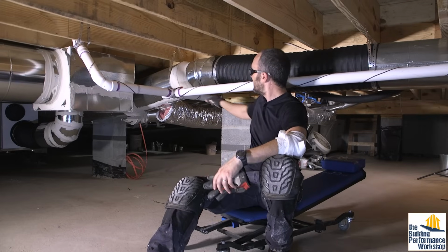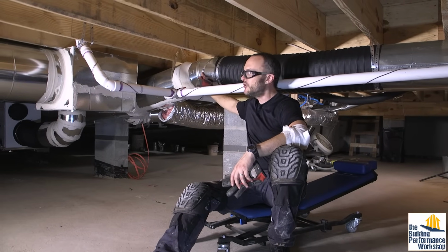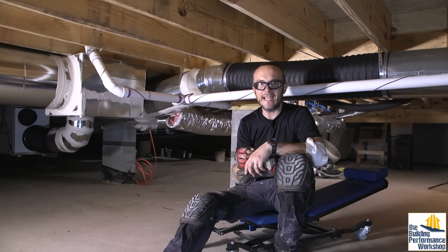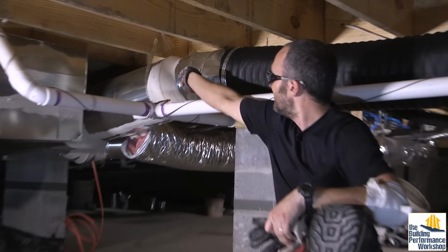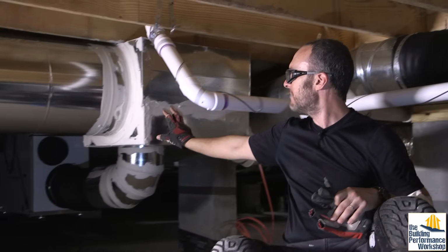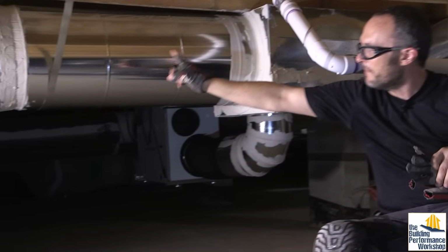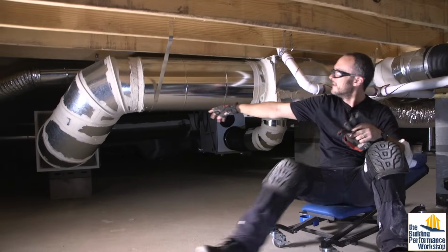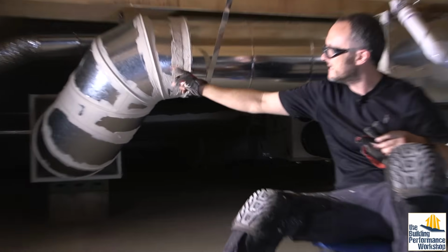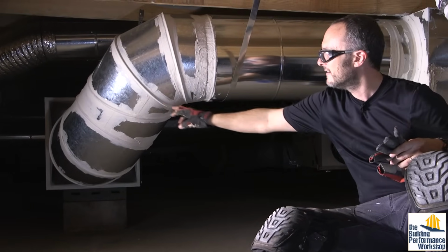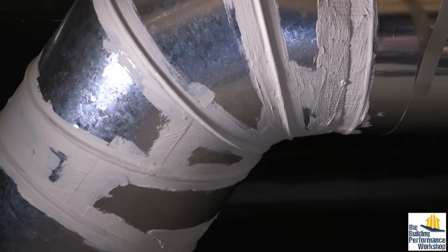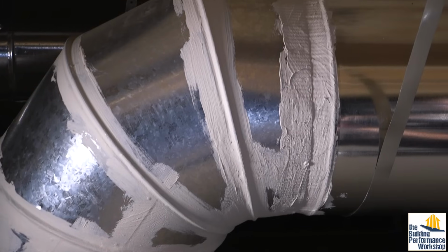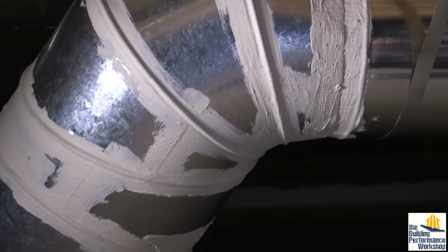So you can see here that this is not sealed. Do not ever think that ductwork, just because it snaps together and it sounds like it has a good lock on it, is airtight at all. This all needs to be masticed so that it starts to look like this box and the rest of this main trunk line to the heating and cooling system. You can see that we've sealed up every one of the seams between pieces of ductwork, every one of the turning points on an elbow, these little seams on the elbows as well, and every one of the fasteners too. So right now, I have been through about 7 gallons of mastic on this house, and I am not done yet. I think I might need another gallon.